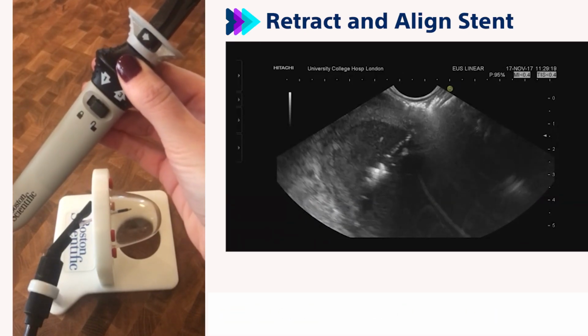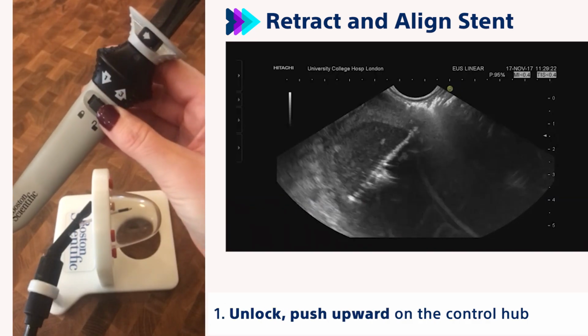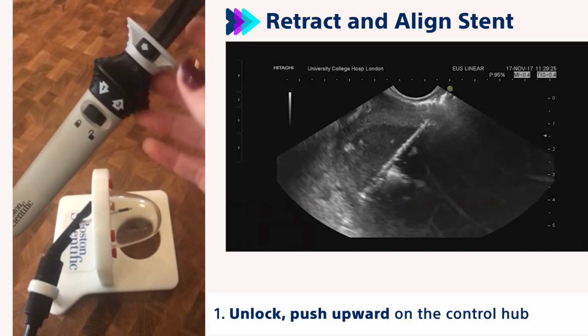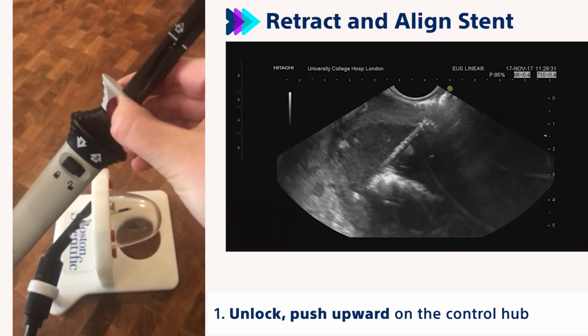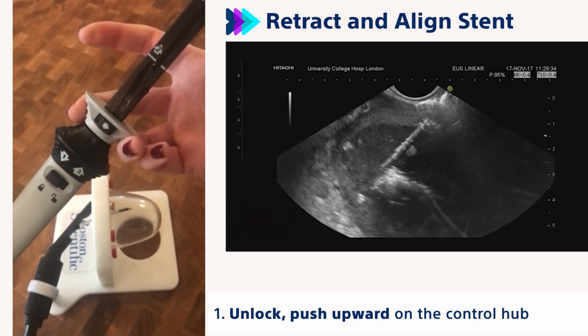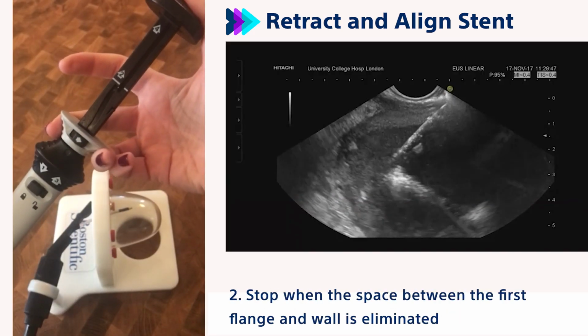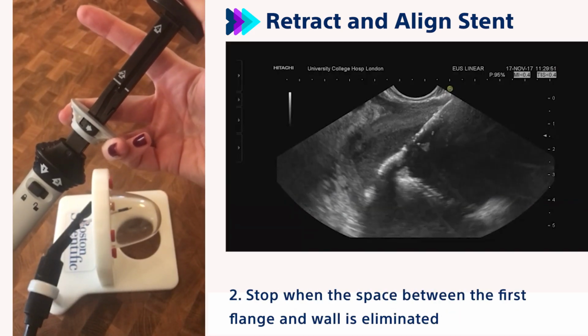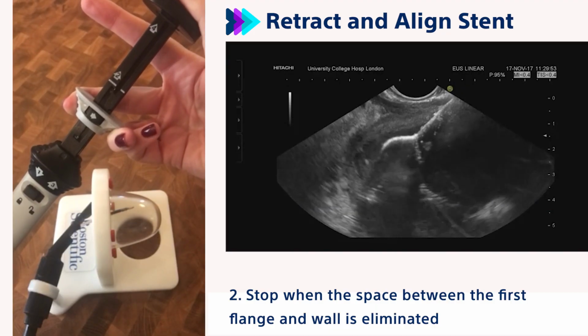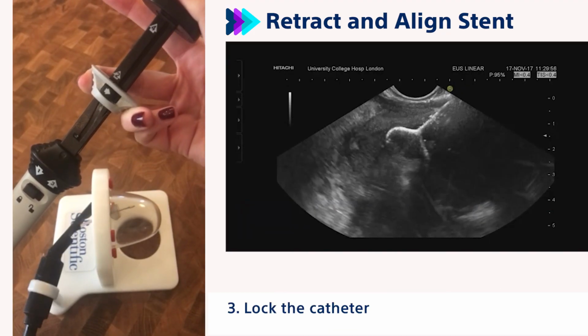To retract and align the stent, unlock the catheter lock. Push upward on the black control hub to bring the first flange so it is gently against the inner wall of the structure. Stop retracting when the space between the flange and the wall is eliminated, and the inner catheter shifts slightly to the left of the flange, and lock the catheter lock.